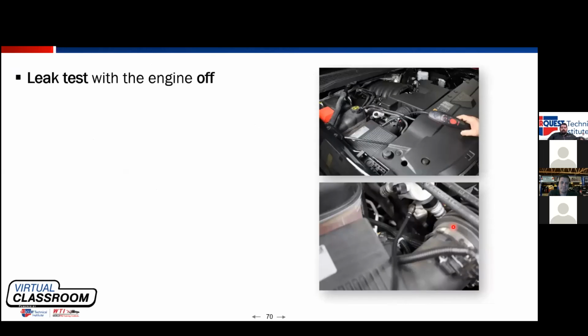Best practices for leak detection. We generally want to leak test with the engine off if we're doing electronic leak detection. One of the reasons is that if you're running the engine with the engine cooling fan running, any refrigerant that is leaking can be dispersed. The other thing is, depending on your leak detector, air movement at high speed, like from an engine cooling fan, can false trigger your leak detector. So we want a still environment, block off any drafts.